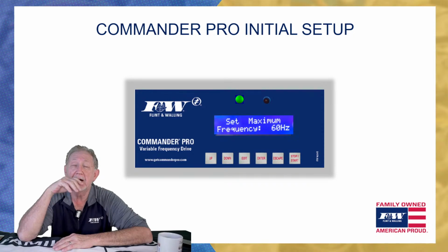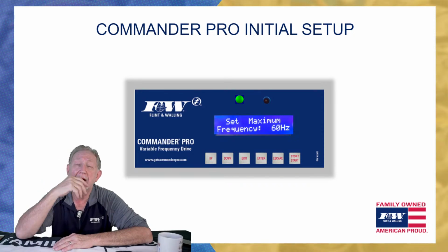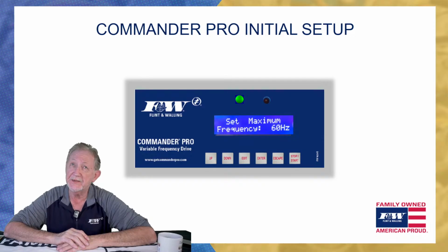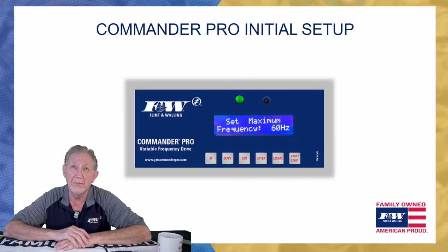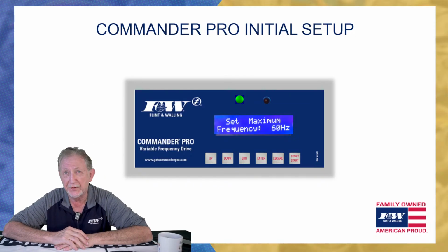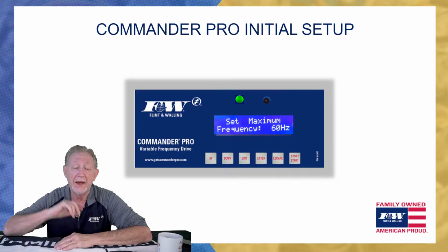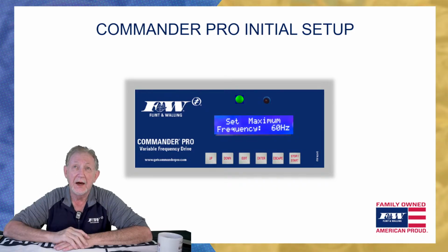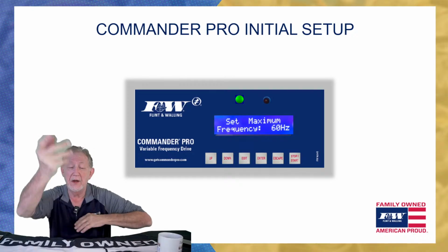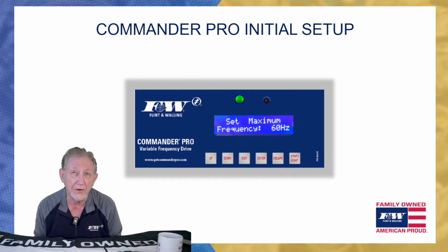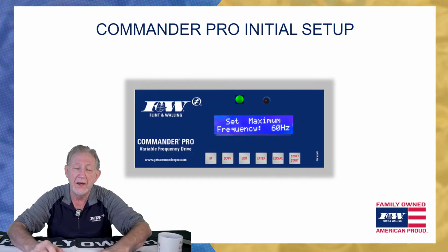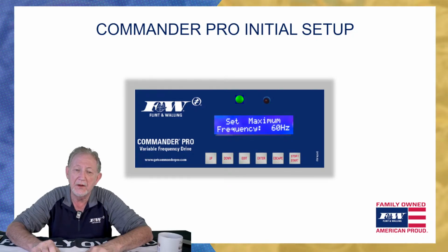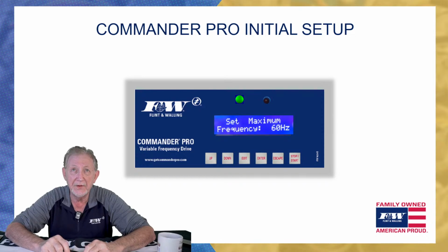Flint and Walling not only does it this way, but we historically, very successfully, have run mismatched pump ends and motors. We'll take a 3/4 horse pump and throw that on a 1.5 horse motor, and then we just spin it faster. We get a lot of efficiency out of it that way, but we'll run that thing all the way up to 80 hertz. All right. So again, if you're running a matched pump and motor by horsepower, then you're going to run that at 60 hertz. If it's mismatched, you'll run it up to 80 hertz.